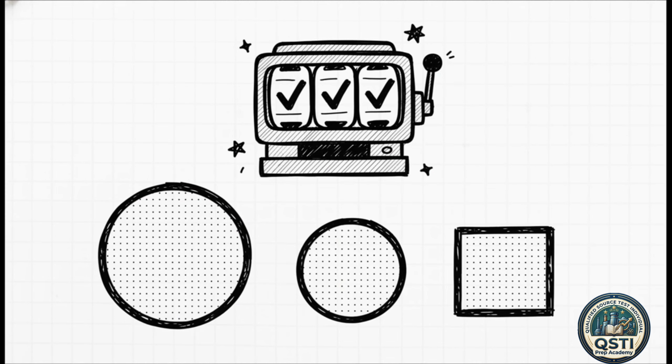Let's say you hit the jackpot and actually meet that perfect 8 and 2 rule. Well, Method 1 rewards you. For massive stacks, anything over 24 inches in diameter, you only need a minimum of 12 traverse points. For smaller circular stacks, sitting between 12 and 24 inches, you just need 8. And if you've got a small rectangular stack in that same range, it's 9 points minimum. Hitting those 8 and 2 criteria is a huge win because it saves you a ton of sampling time out in the field.